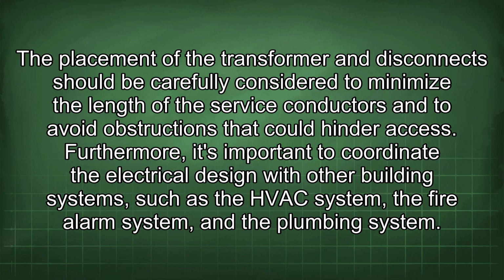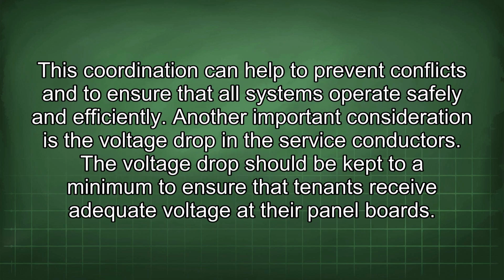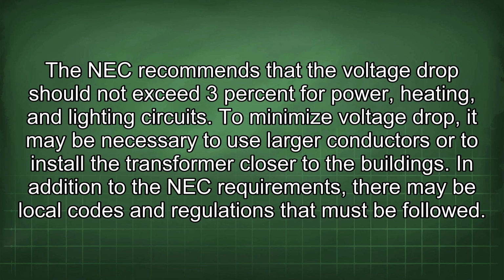Furthermore, it's important to coordinate the electrical design with other building systems such as the HVAC system, the fire alarm system, and the plumbing system. This coordination can help to prevent conflicts and to ensure that all systems operate safely and efficiently. Another important consideration is the voltage drop in the service conductors. The voltage drop should be kept to a minimum to ensure that tenants receive adequate voltage at their panel boards. The NEC recommends that the voltage drop should not exceed 3% for power, heating, and lighting circuits.